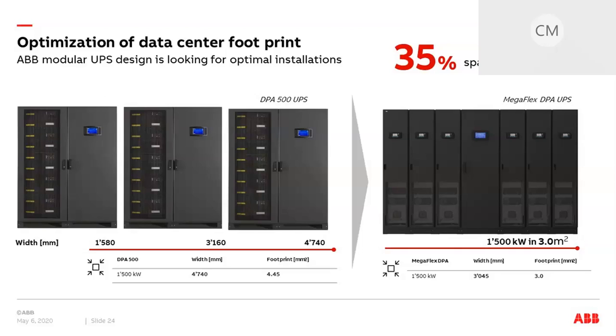In the example that we are showing, there is a solution of a 1.5 megawatt UPS, which can be implemented by paralleling 3 DPA UPS for a footprint of 4.45 square meters, or with a single MegaFlex DPA with a footprint of 3 square meters. When we take the latest UPSs, we are able to provide up to 35% space saving for the installations.